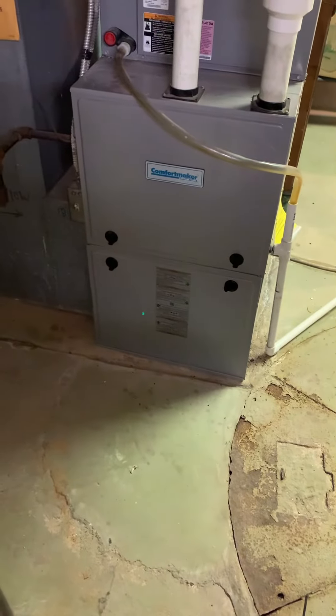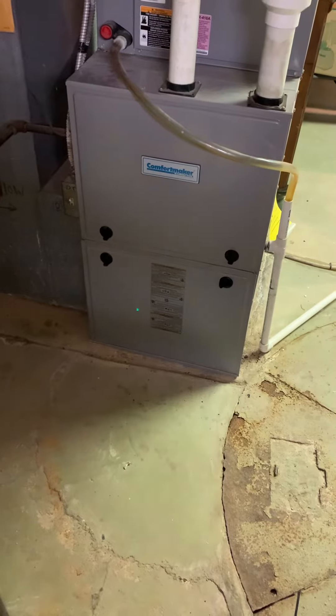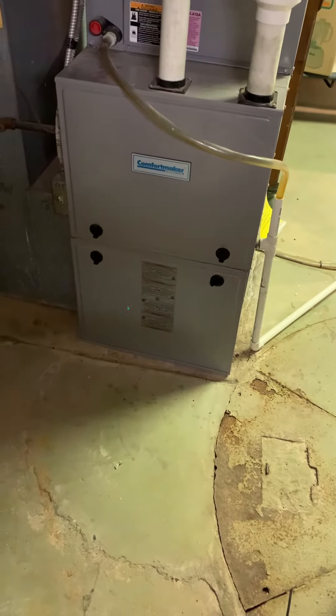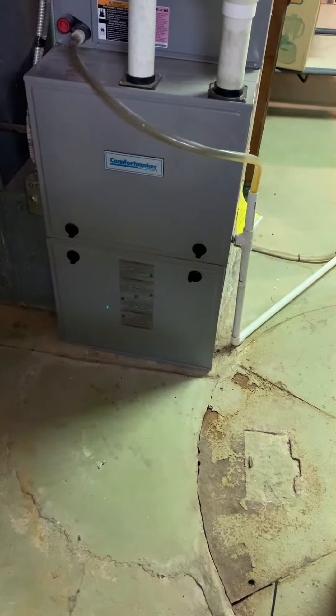Taking a look at unit number one. This does some of the first floor, about 1,000 square feet. This is a 100,000 BTU furnace, quite a bit oversized I would say for the area, and it only has six runs off of it.